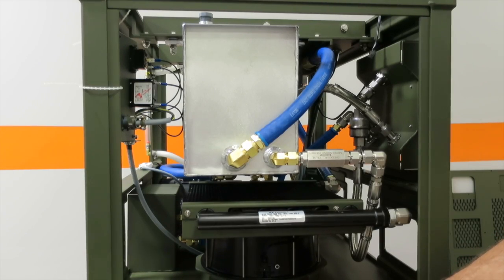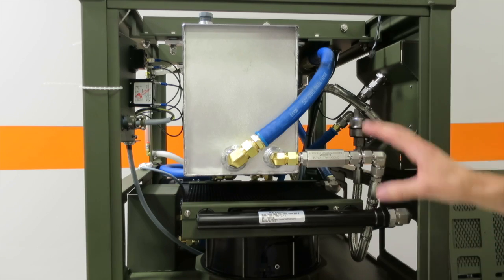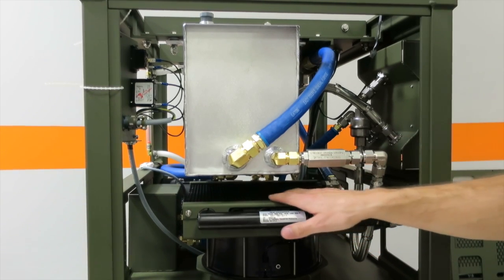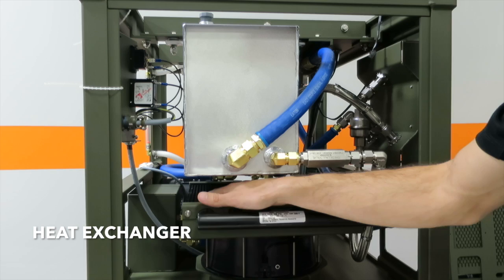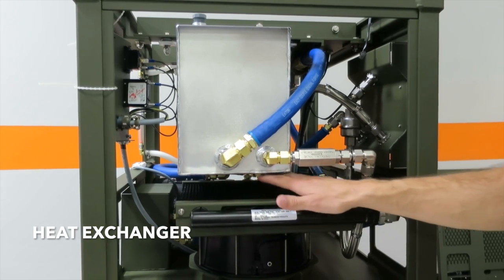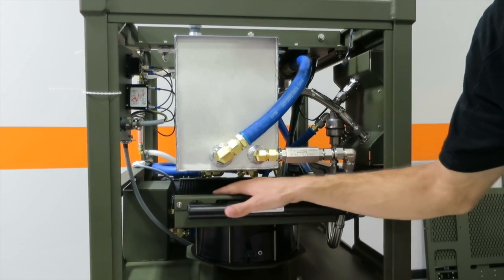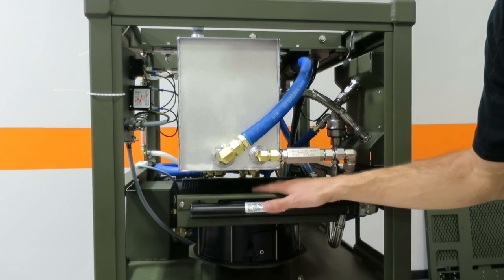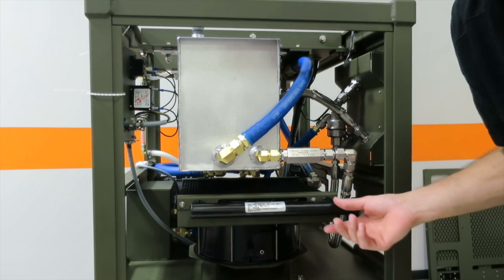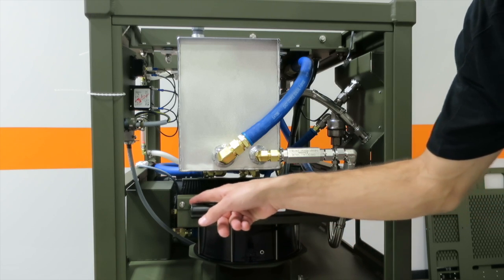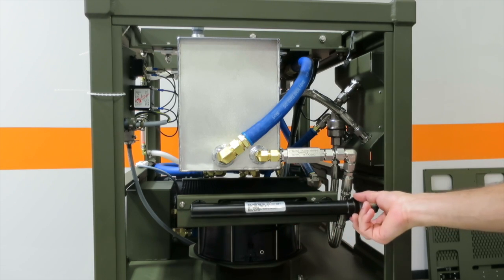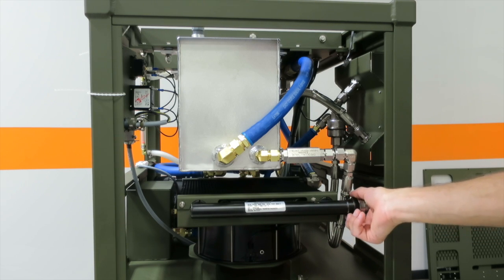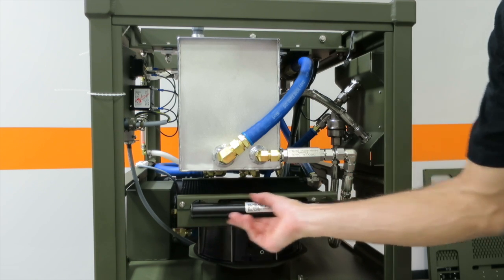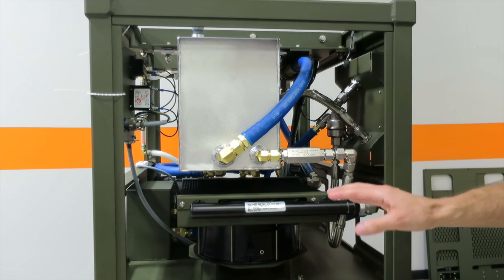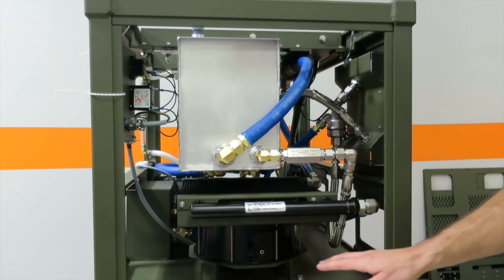And now we're talking about the back of the water recovery system. We're going to go through some of these components. So right here we have the heat exchanger. All these fins on top are aluminum fins, so they're kind of delicate. If you're ever cleaning this out or removing this, just be careful of those. All the tubes are copper tubes, but this is actually pretty vulnerable to being bent. So if you're ever working on this heat exchanger, remember to counter torque and be careful with it.